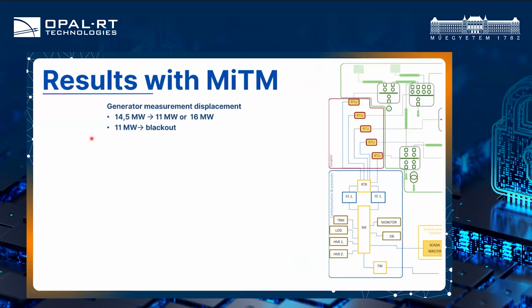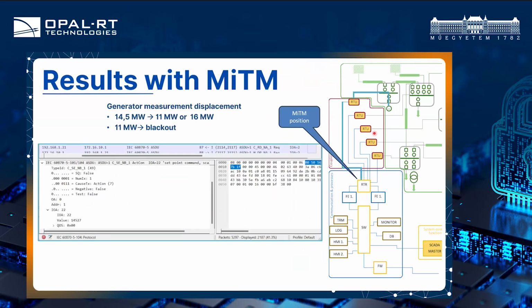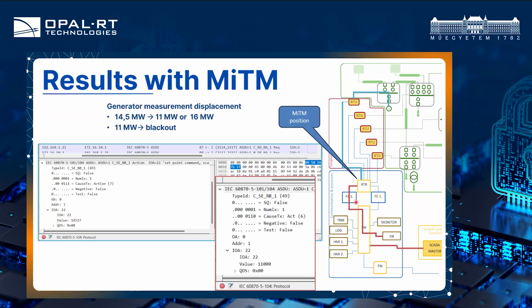Let's see what we have achieved with this man-in-the-middle position. We have changed the measurement from the generator. So here we are at the man-in-the-middle position. We have seen that this information goes through the RTUs and comes to the router. Here we can see a Wireshark window of it, and the actual packet here displays a little over 14 megawatts. The script changes this value to 11 megawatts, and this is fed to the database, and the control algorithm sees this value inside.